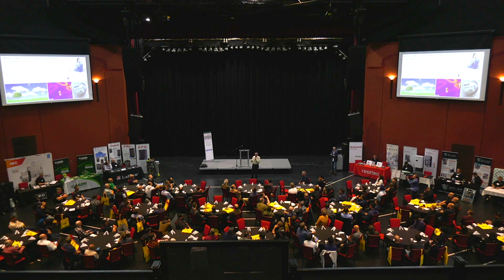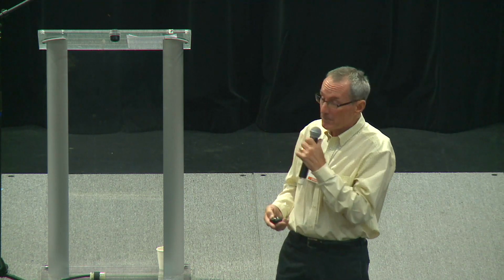How many have heard that term, distribution efficiency? Anybody? We've been writing about it a little bit. It's a really simple idea. You simply take the BTUs per hour that you're delivering, let's say at design load, and you divide it by the electrical wattage that operates your distribution system, not your source. It has nothing to do with the source energy. It's how much power goes in to move that heat from where it's produced to where it needs to go in the building. And hydronics is easily a 10-to-1 advantage over air in that category.